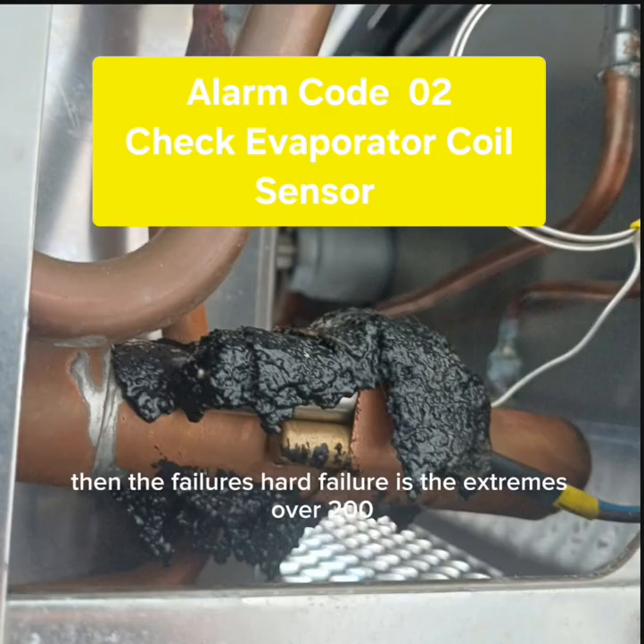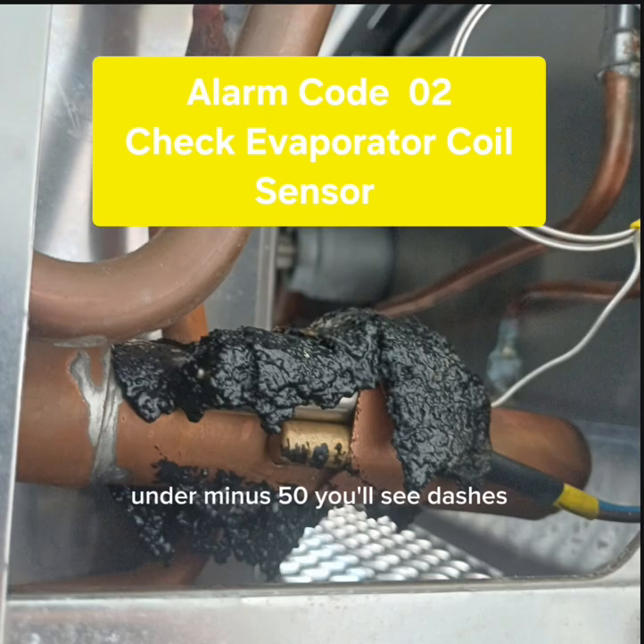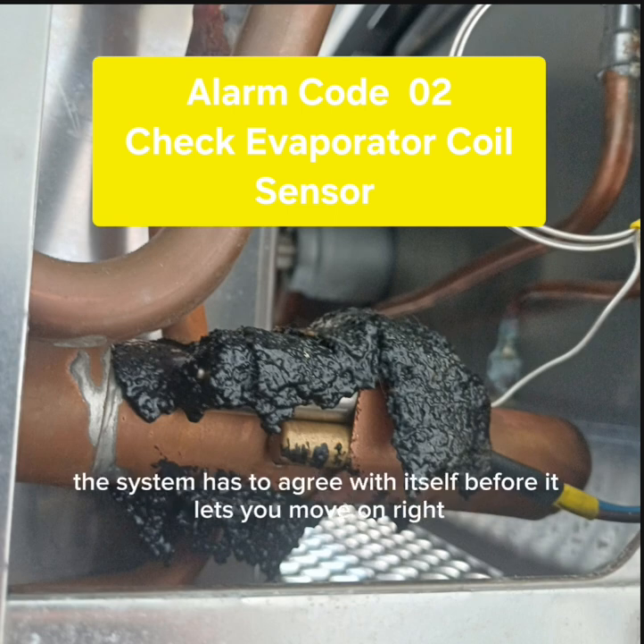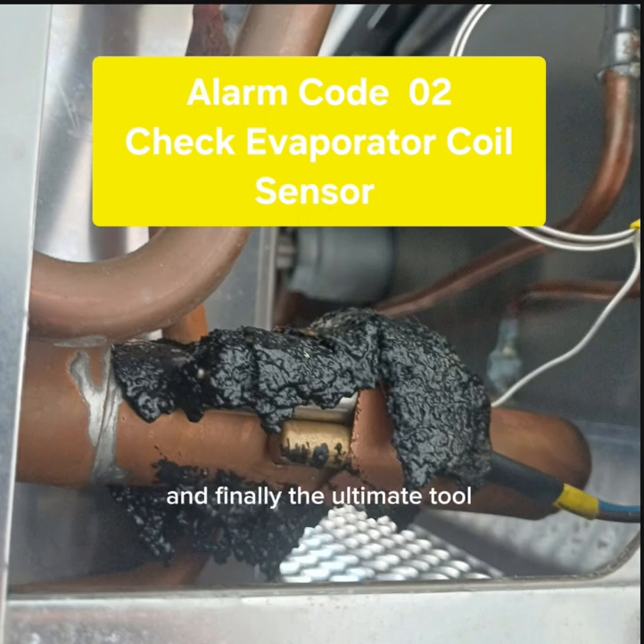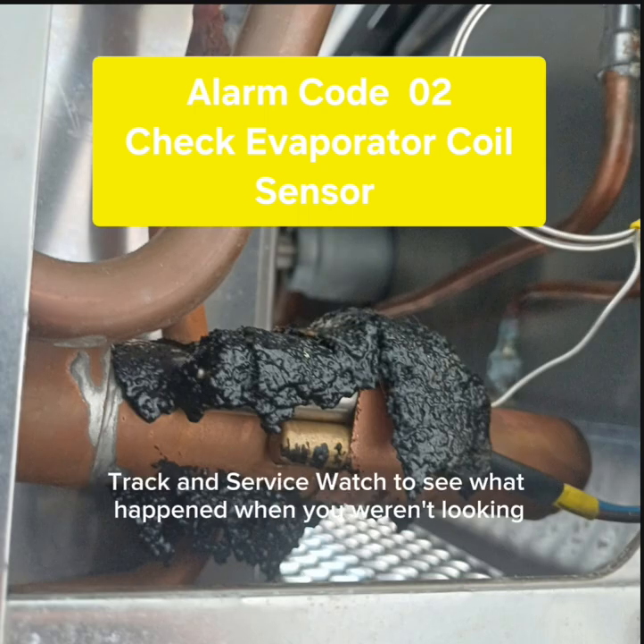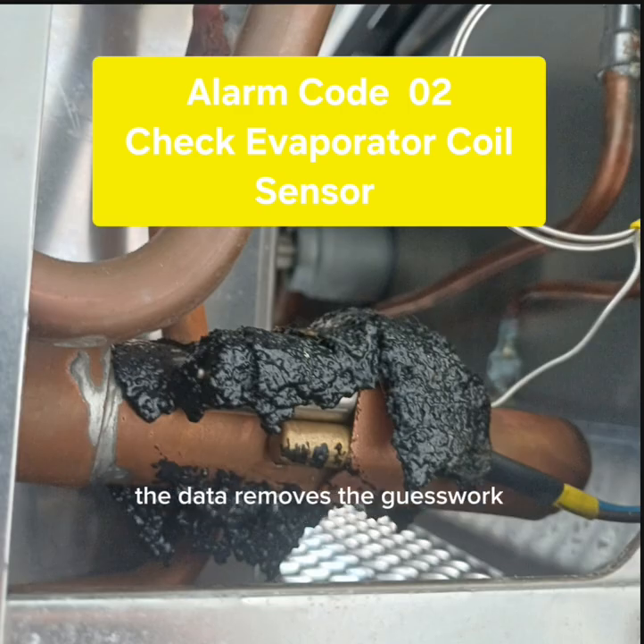Then the failures. Hard failure is the extremes, over 200, under -50, you'll see dashes. Soft failure is the drift, usually with alarm 13. And don't forget the clearing logic. The 30-degree rule. The system has to agree with itself before it lets you move on. Right. And finally, the ultimate tool, data. Use WinTrack and Service Watch to see what happened when you weren't looking. That's the most important part. The data removes the guesswork. It turns I think into I know.